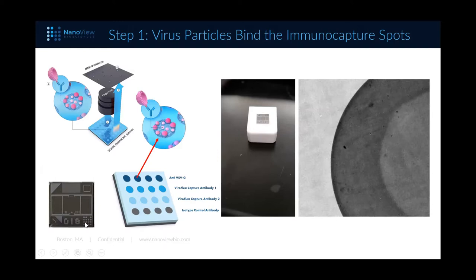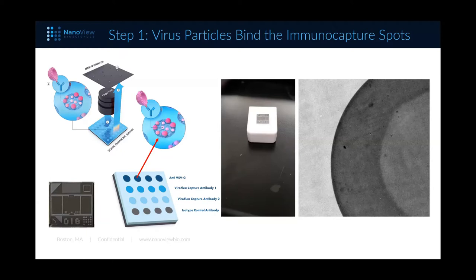The core of the technology is the single chip — single-use chips that come functionalized out of the box with a microarray on them. The microarrays are mostly antibody arrays, though other capture types can mediate binding too. During the sample incubation stage, all we do is take out a chip — seen here placed on top of a thumb drive — and on that chip is a multi-spot array of different capture types. In the Lentiview assay, the anti-VSVG capture row in dark blue is the primary spot of interest.